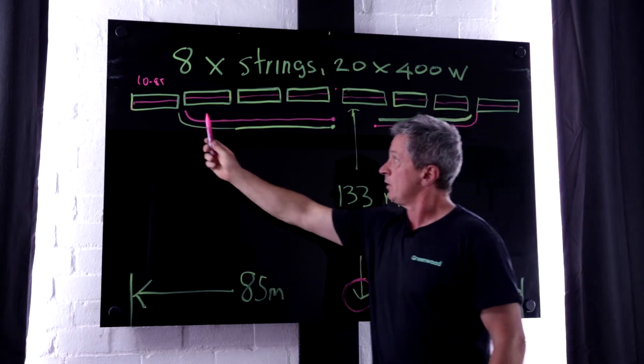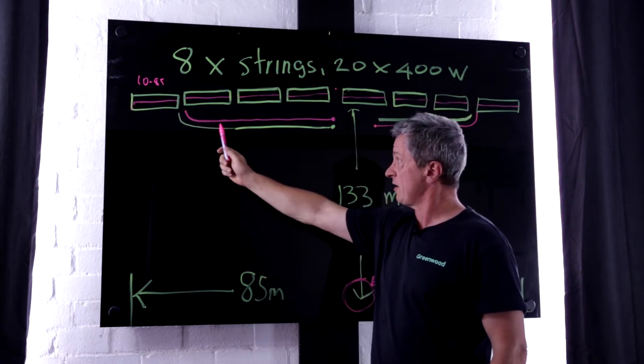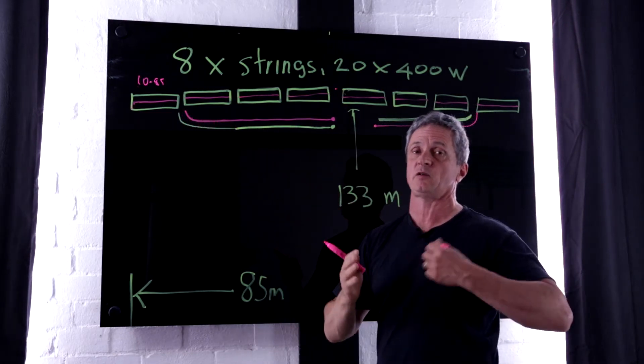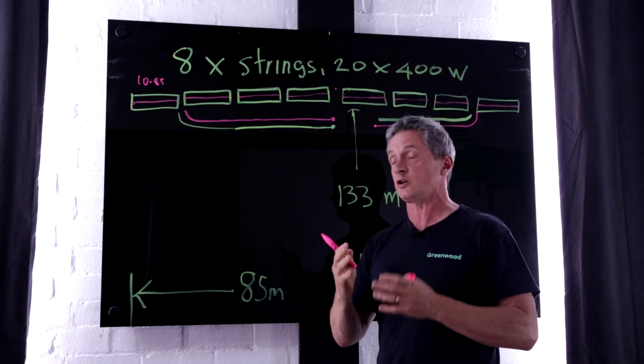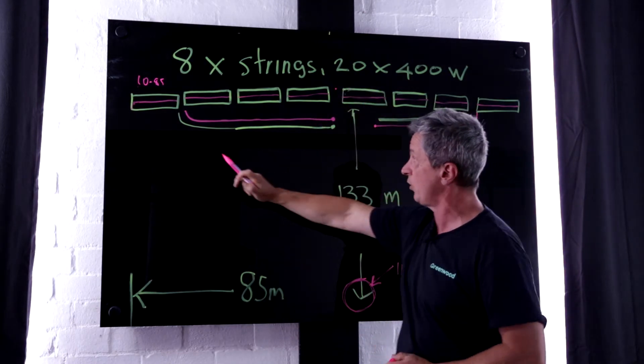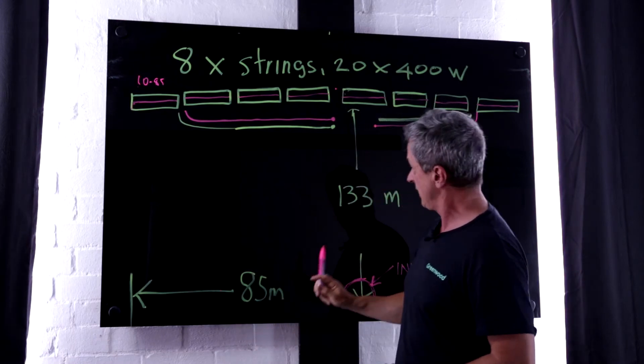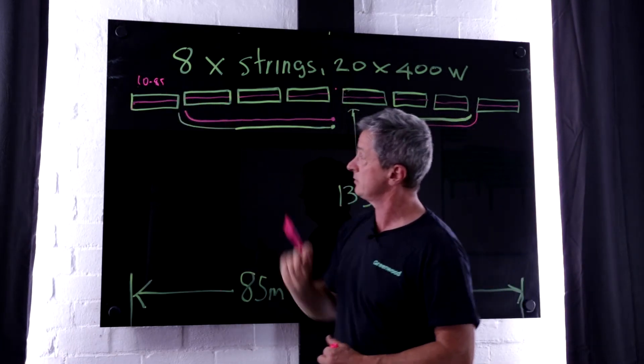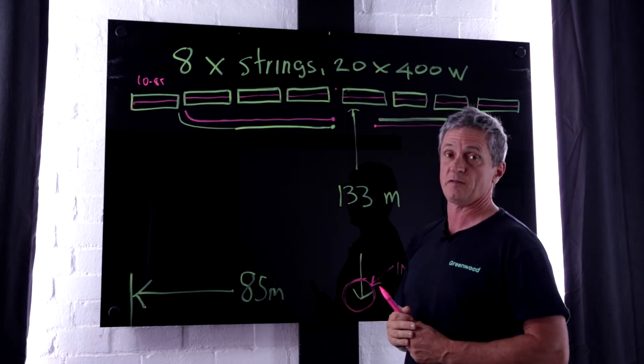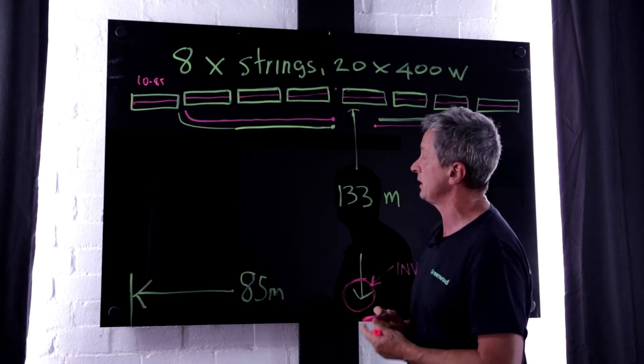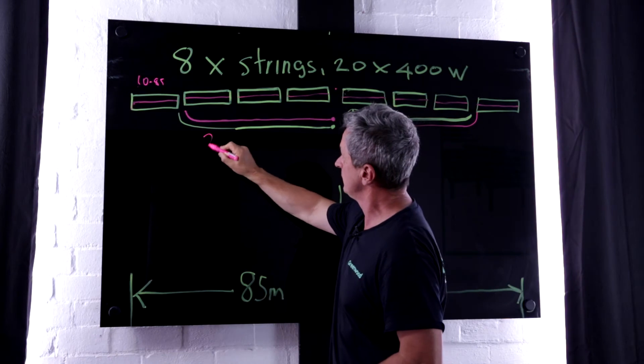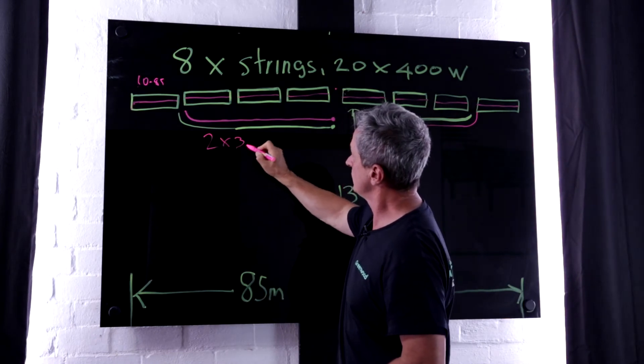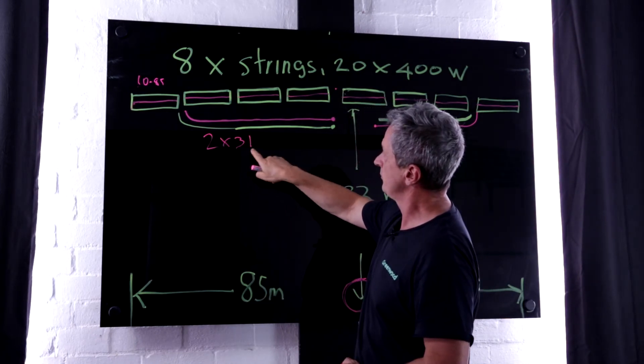So this run here, positive, negative, take into consideration, no bends and curves when it gets to this central point, is 42 metres minus 10.85. So it's about 31 metres approximately. So we have two cables, 31 metres.